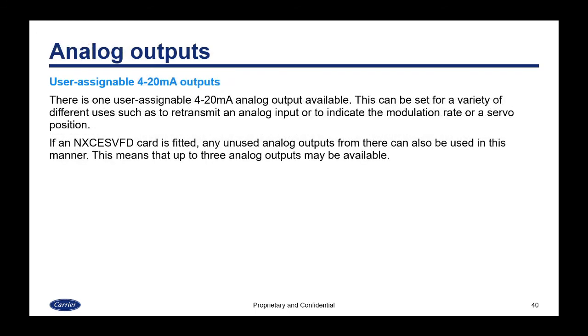There are also user assignable 4 to 20 milliamp outputs, and there is one user assignable 4 to 20 milliamp output by default. And these can be set for a variety of different uses, such as to retransmit an analog input, or to indicate the modulation rate or a servo position.